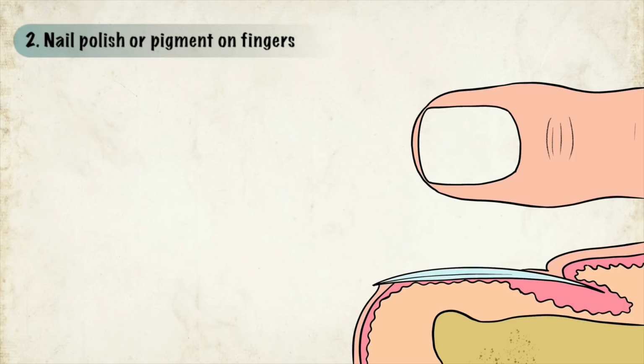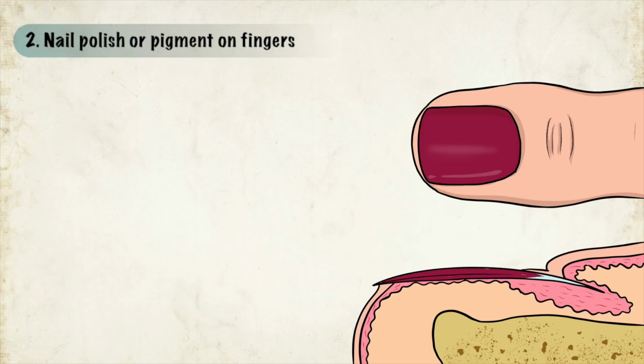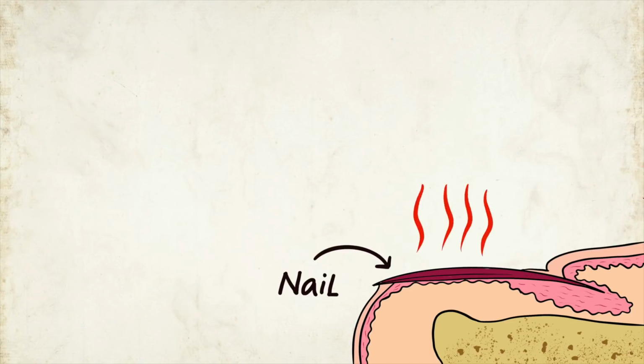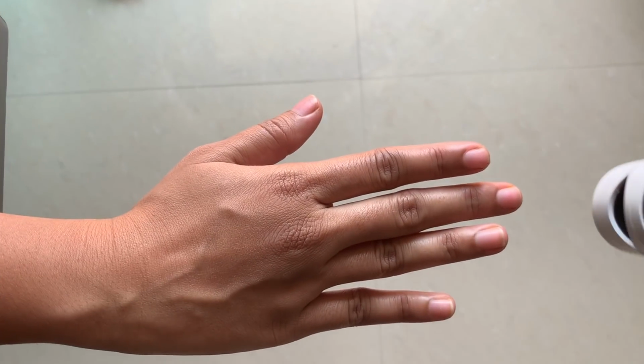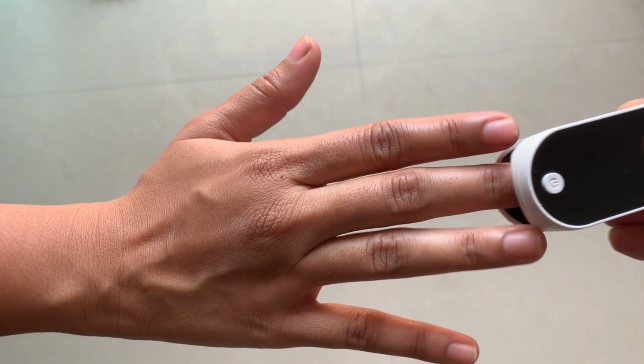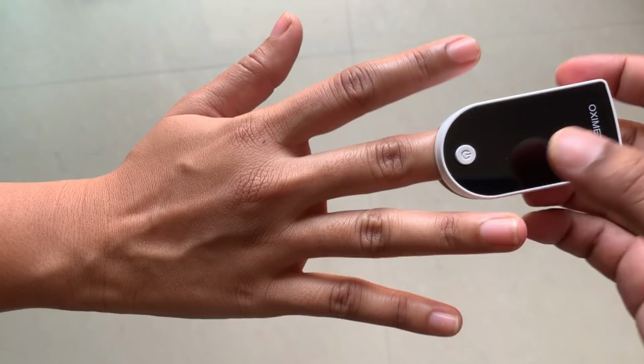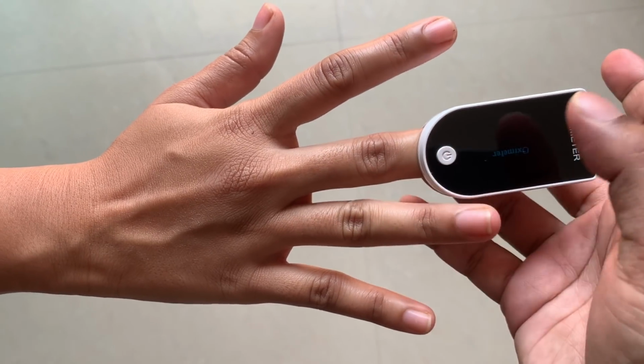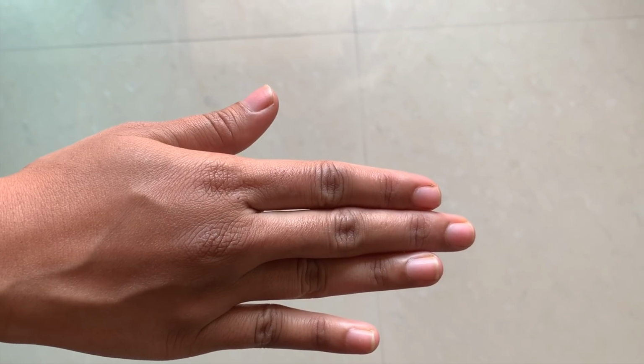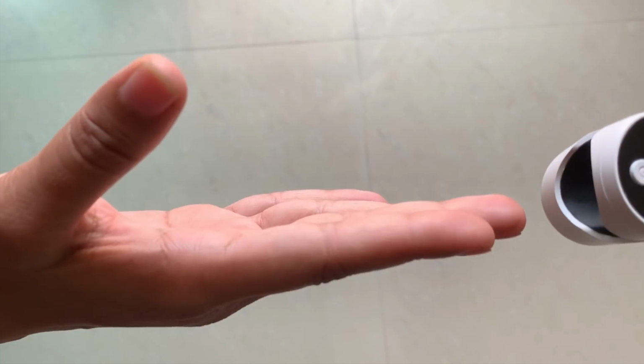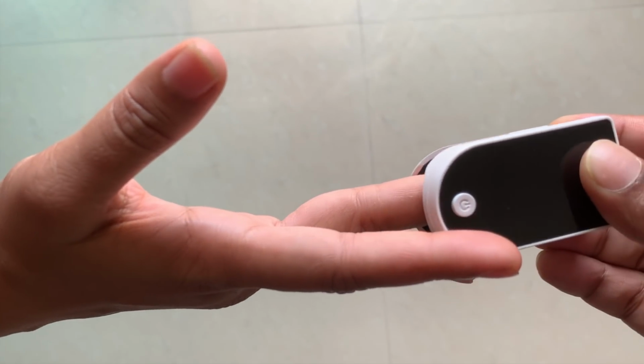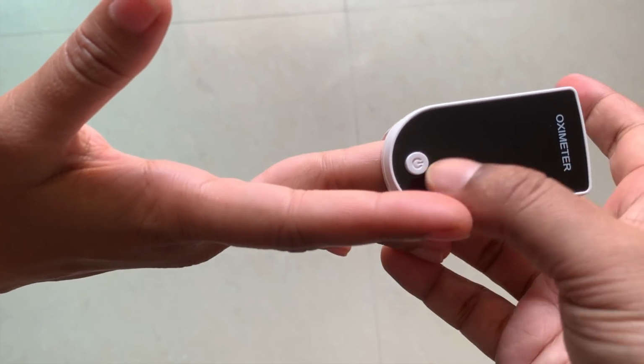Now let's see how nail polish or pigment on fingers can affect the reading. The nail polish color can absorb light emitted by the oximeter and interfere with the detection of oxygenated hemoglobin. So it is always best to remove nail polish from one finger, but in case of an emergency, the probe may be turned sidewise. Here you can see in this demonstration, or use another side if possible.